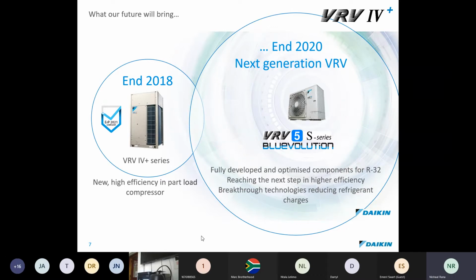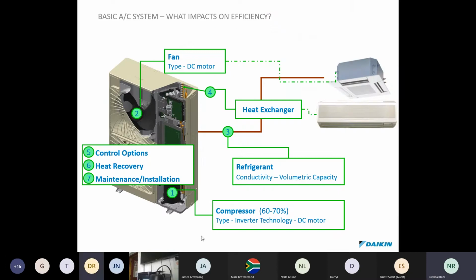The discussion about R32 and its benefits is a topic for a different discussion, but in a nutshell, it's more efficient, uses less charge, and is more ecologically friendly. So back to an air conditioning system. Most people know that the compressor, or the outdoor unit as most people call it, is the heart of any air conditioning system, and that's where the most energy is used, right? So what would impact the efficiency? Number one, the fan. It's the fan, the heat exchanger, the refrigerant that's used, and the actual compressor.